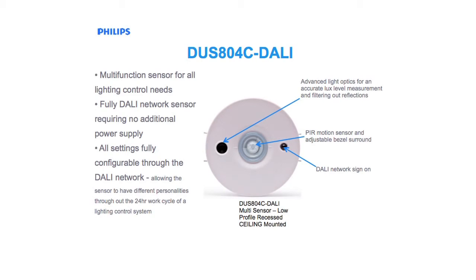The DUS804C DALI is a multifunction sensor, able to perform both daylight harvesting and PIR motion detection at the same time. This allows the sensor to automatically start a daylight harvesting strategy once motion is detected. The sensor is fully networkable and does not require any manual adjustments. All settings are completely configurable by the commissioning or head-end software. This allows the sensor to have multiple configurations throughout a 24-hour work cycle.